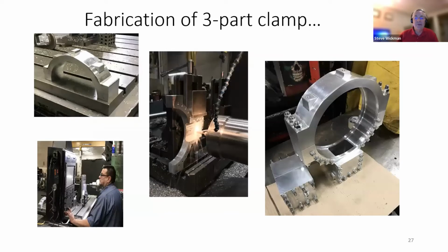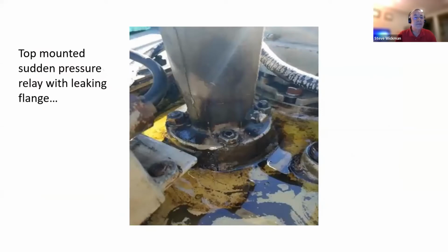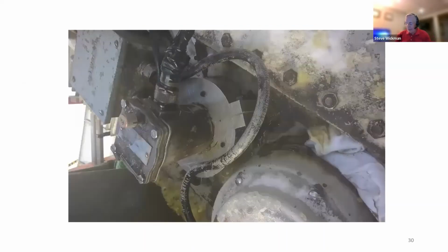Here's that clamp fabricated at the one machine shop that we often use that's here in suburban Chicagoland. CAD design put into their CNC machines, and then they machine this up for us to get it shipped out to the site. Here's that sudden pressure relay that I showed you earlier with that leaking flange. And here's the clamp that was created to contain that leak.